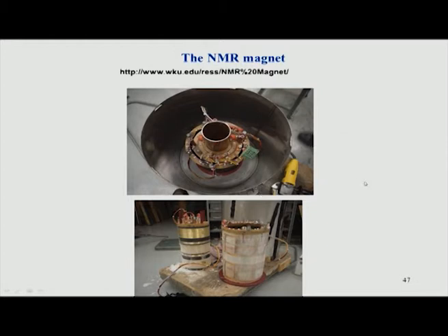The liquid nitrogen helps in reducing the evaporation rate of liquid helium, and then again you have a vacuum and so on. So, you have different concentric layers to prevent the liquid helium inside the innermost container from starting to evaporate. But of course, one cannot avoid evaporation. So, liquid helium very slowly evaporates and one has to refill helium once in a few months, because slow evaporation is always unavoidable.